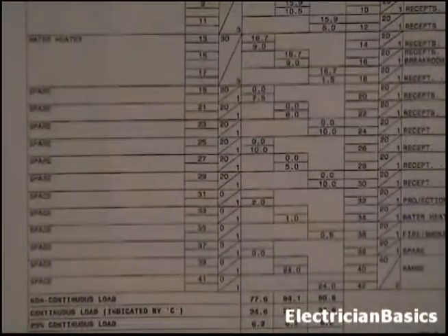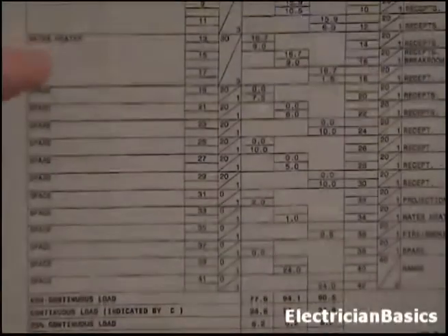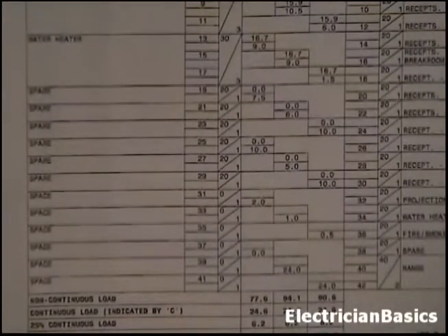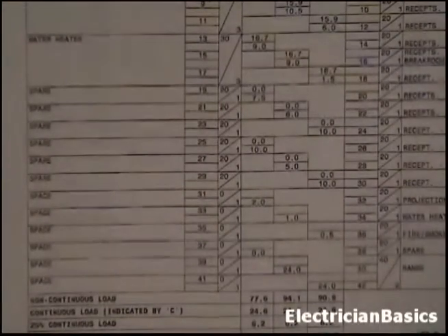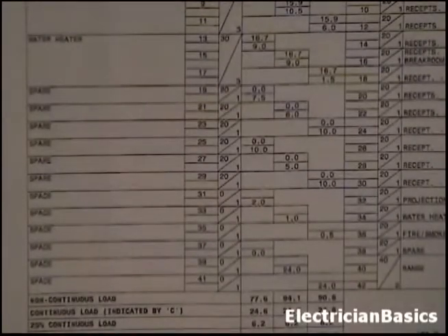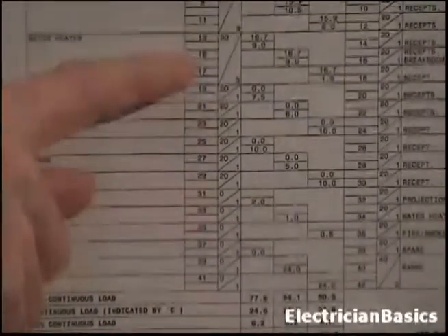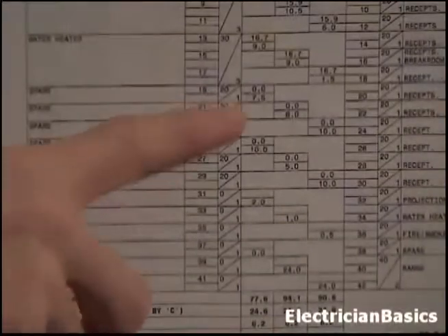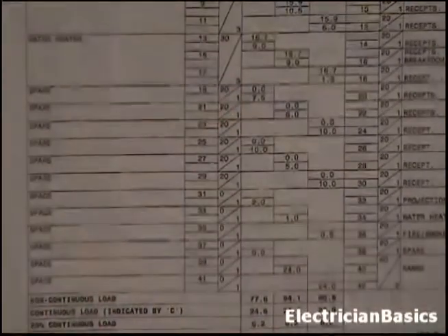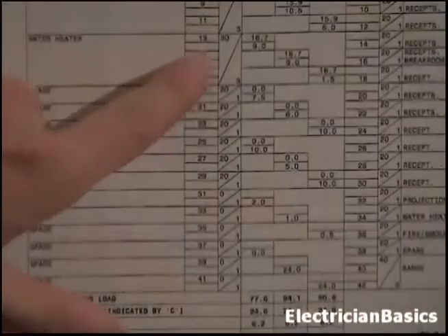Okay, now we're going to stay with panel E5. We've just moved over a little bit. We've got the water heater. How many circuits feed that water heater? What type of breaker? It's 3 circuits, 13, 15, 17. It's a 3-pole breaker. It's a 30 amp breaker.